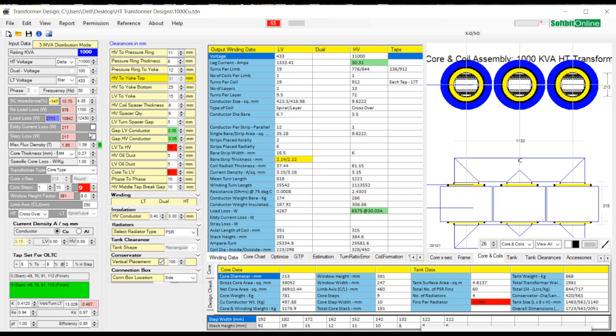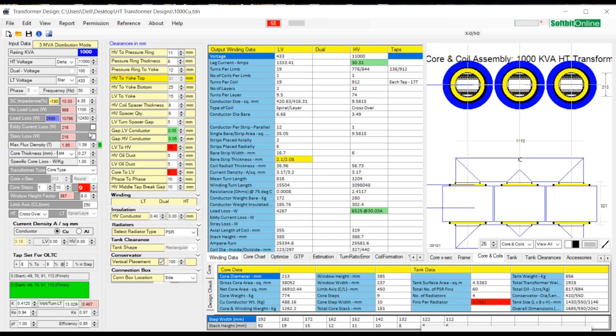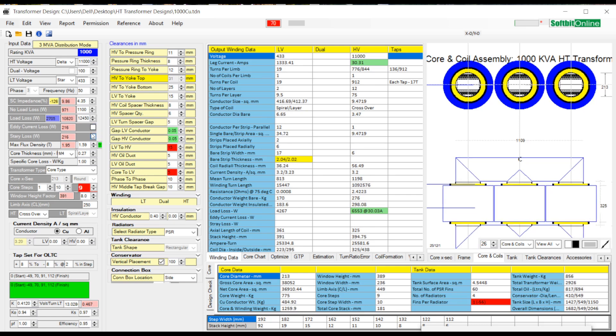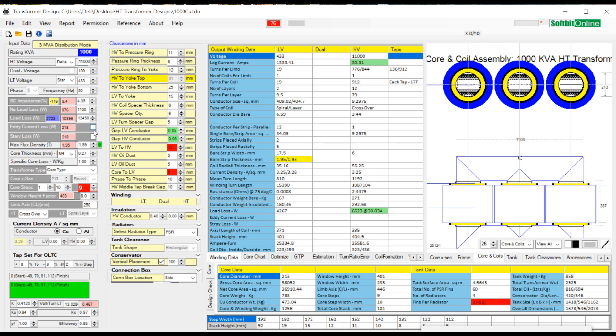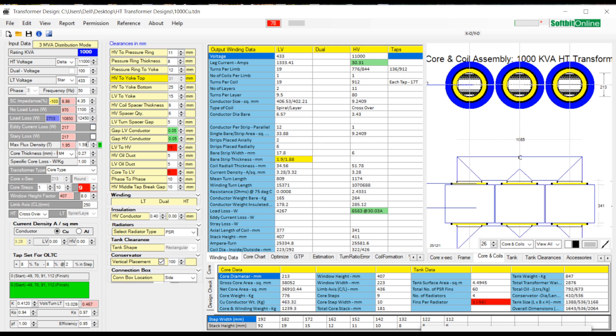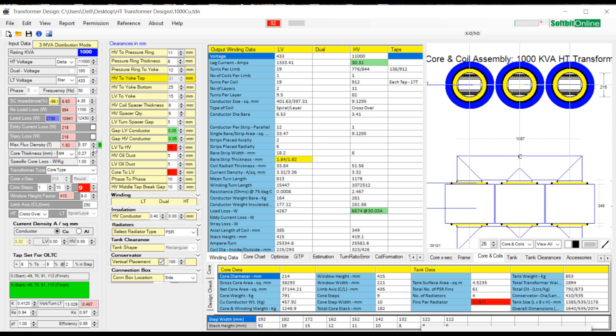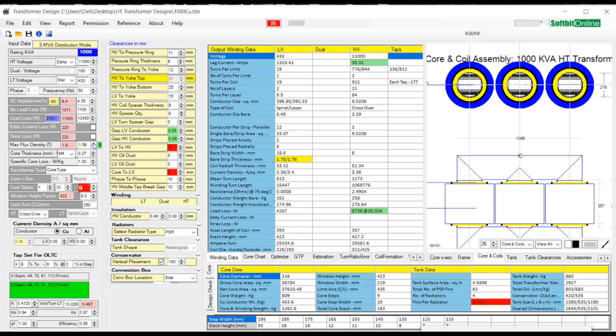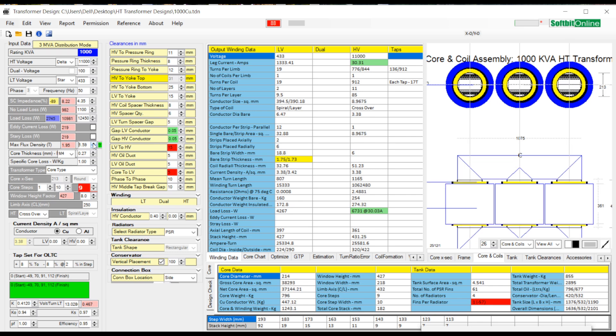Next comes flux density. The value of flux density is taken in Tesla and varies between 1.5 to 1.65 depending upon the client specifications and rating of transformer.